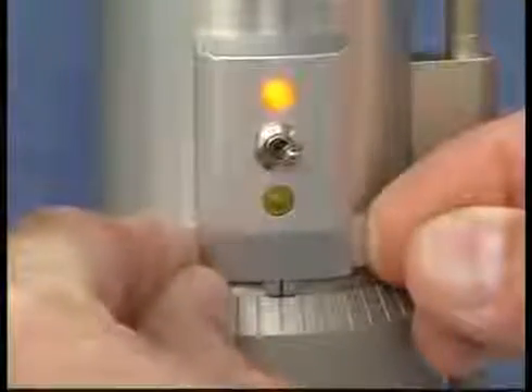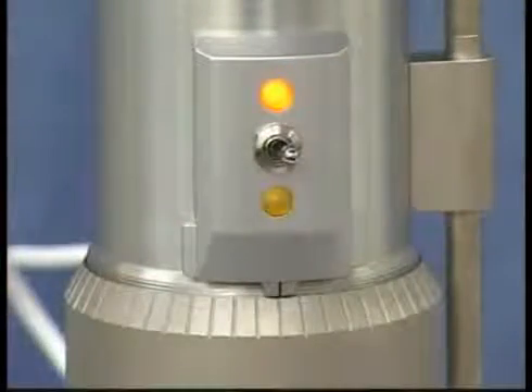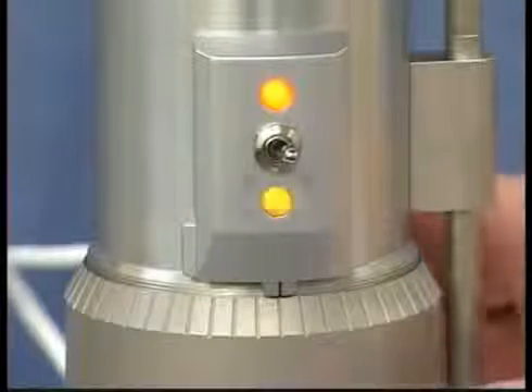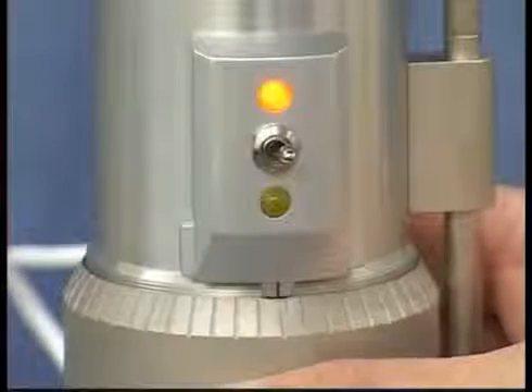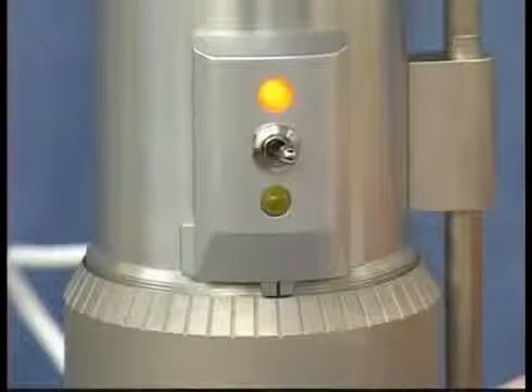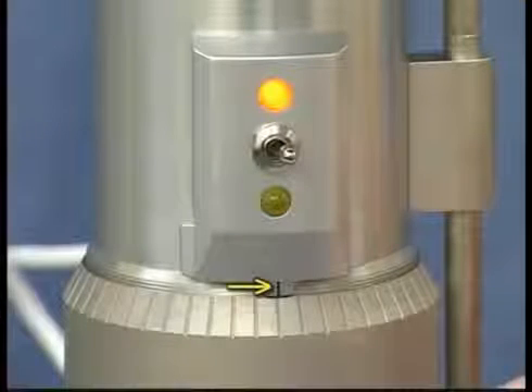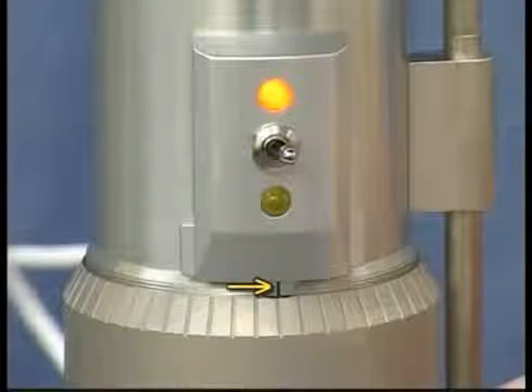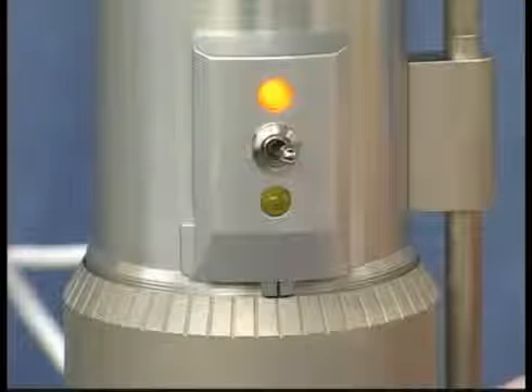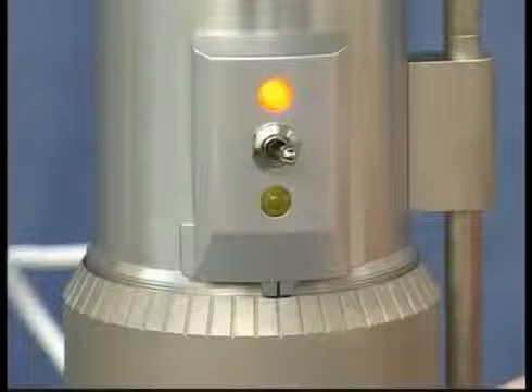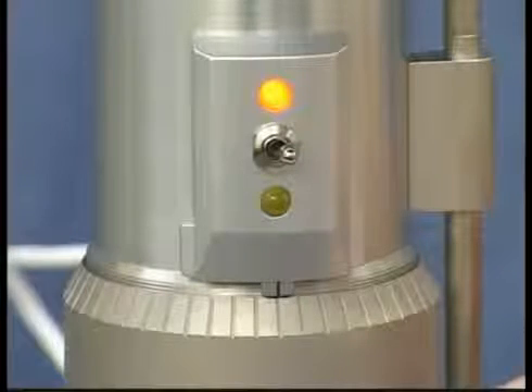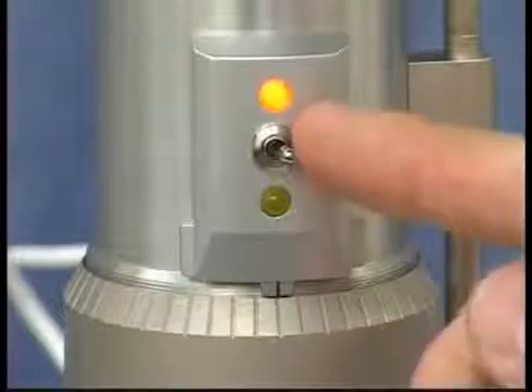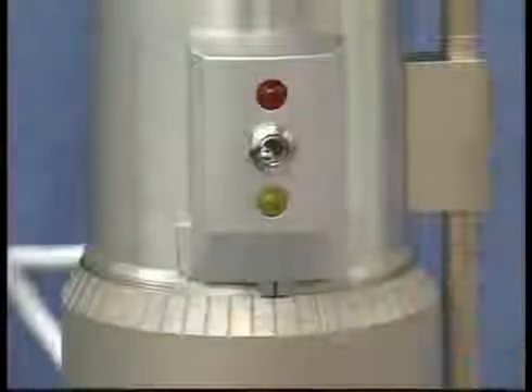Adjust the sliding reference marker, right or left, to the closest full-scale division mark. Now, turn the micrometer adjustment ring 1 scale division to the left to meet the line on the sliding reference marker. The yellow light should go off. You have established the gap. Now, turn the toggle switch to the left and the red light should go off.